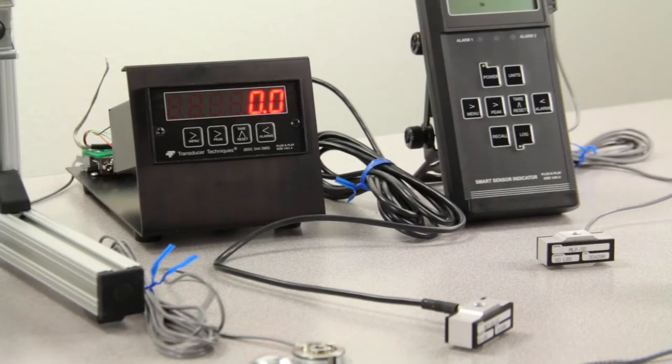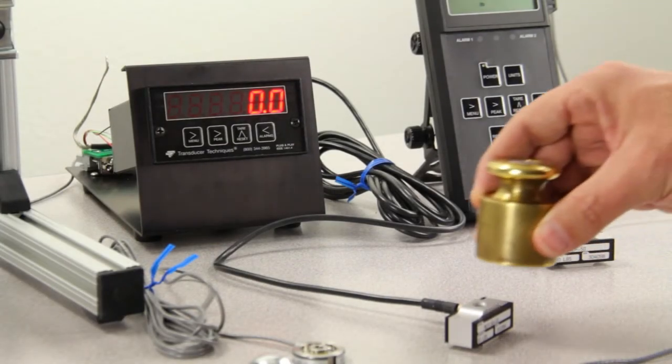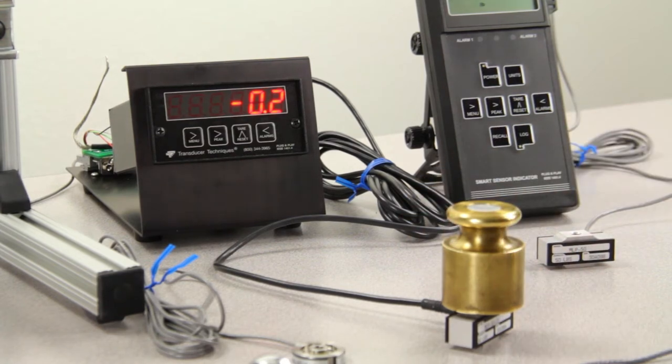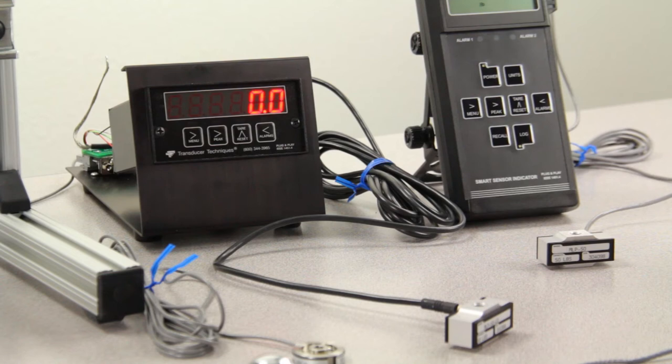Here I have a load cell connected without the smart plug-and-play option. I'll set a 1 pound weight on the load cell. Notice the meter is reading -0.2 pounds. This means the system is not calibrated.